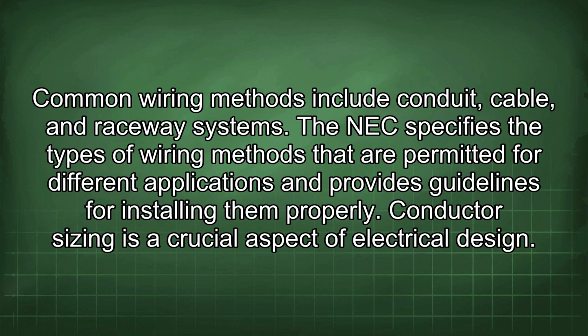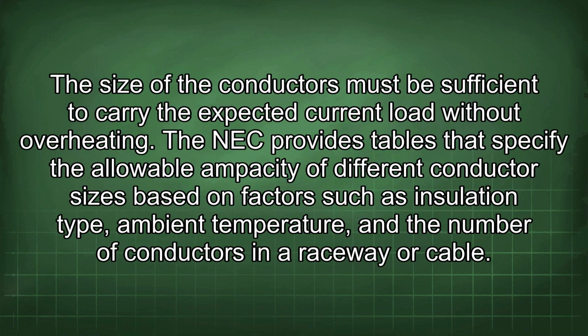Conductor sizing is a crucial aspect of electrical design. The size of the conductors must be sufficient to carry the expected current load without overheating. The NEC provides tables that specify the allowable ampacity of different conductor sizes based on factors such as insulation type, ambient temperature, and the number of conductors in a raceway or cable.